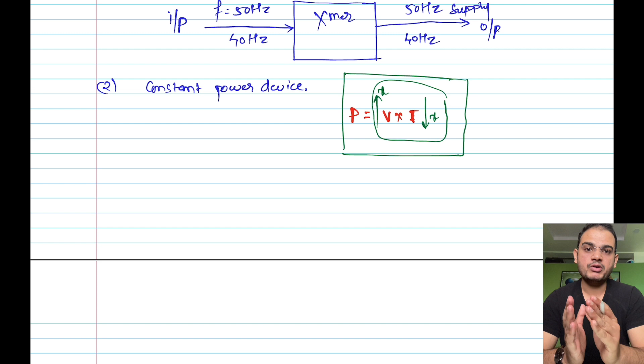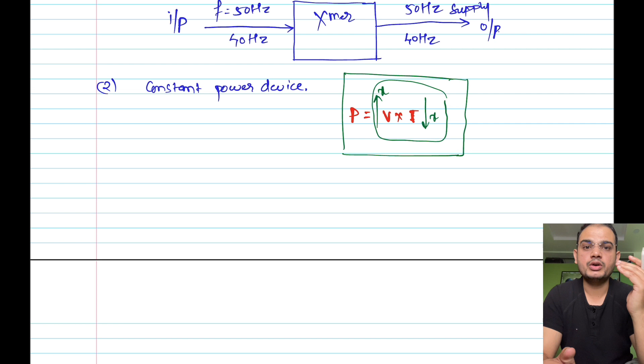Why are we using the transformer in the power system or in the transmission system? In order to decrease the losses and to transmit the power with higher efficiency, with less voltage regulation, with less voltage drop, with less losses. That's why we are using transformers in the system in order to step up the voltage, from 11 kV to 132 kV, from 33 kV to let's say 400 kV. This is how we transmit the power at higher voltage levels in order to decrease the losses. This is how we can understand the transformer as a constant power device.